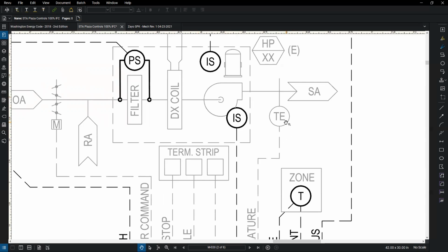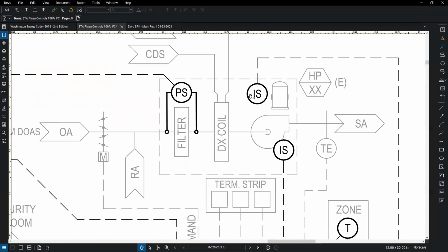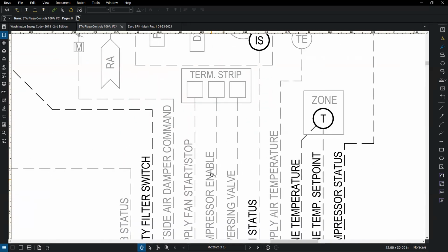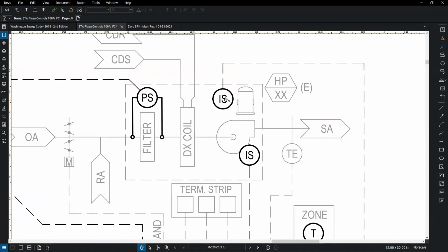We also have a bunch of monitoring points, these TE with the circles. That's a temperature element. So this is plugged into the supply air, so we can see what our supply air coming out of this unit is. This IS is a current switch. So that will tell us when the compressor is running. What that allows us to do is, if we are sending the compressor enable signal, if we're telling the compressor to run, well, that should tell us it's running. If we're telling it to run and it tells us it's not running, well, now we can alarm and say, well, we got a problem here.